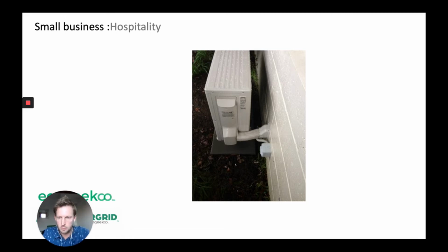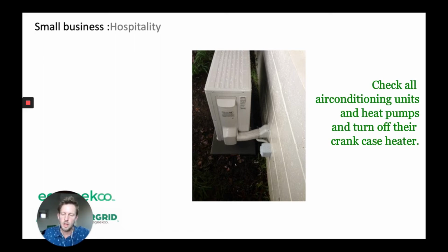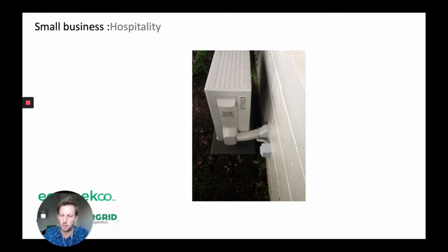The other one, this is often forgotten about, if you have a lot of air conditioning units and heat pumps installed, they have inside them a little crankcase heater. It's a little tiny heater to keep the compressor warm. And the reason for that is so when you start it up, it can run efficiently and quickly. So it keeps the crankcase oil at a certain temperature.